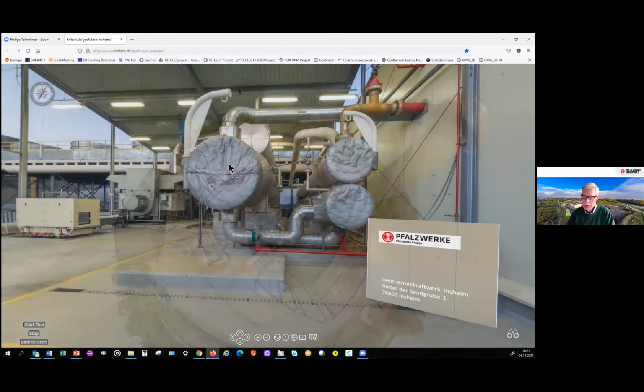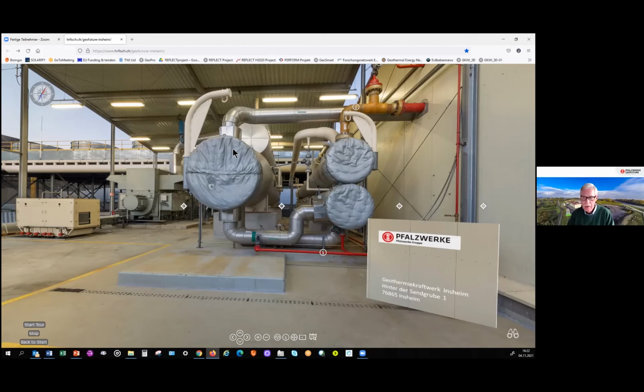So we have tube and shell heat exchangers, and for example in our vaporizer we have roughly 1100 tubes with 1 inch diameter, made of a special stainless steel. These tube and shell heat exchangers allow a very excellent cleaning operation. Plate heat exchangers are definitely more effective, but they're difficult to clean, and especially if you're operating a fluid like our brine with a very high precipitation effect, plate exchangers won't match the product selection.